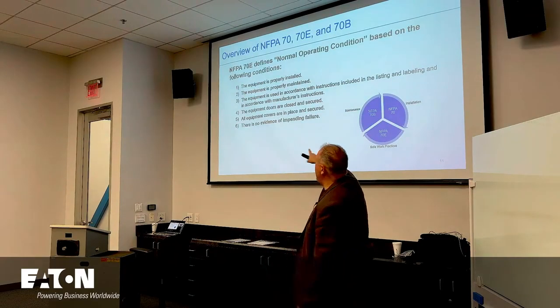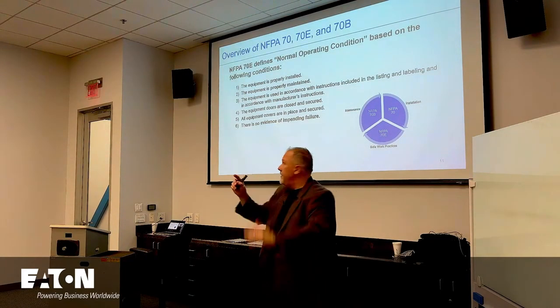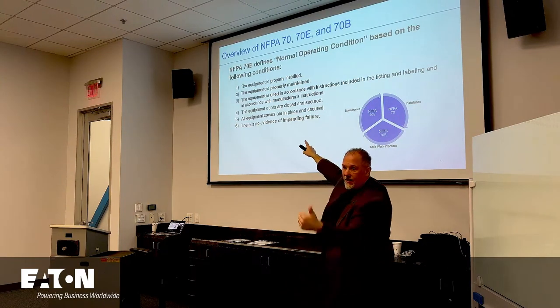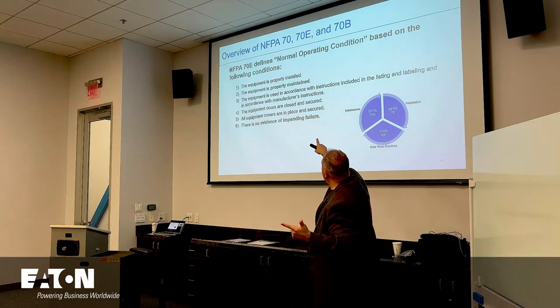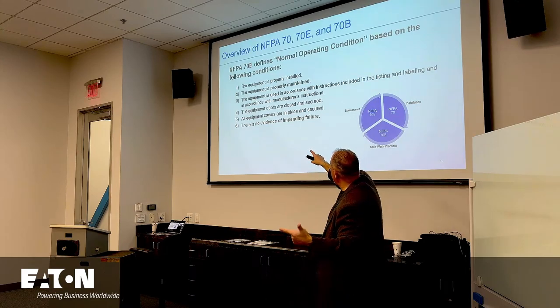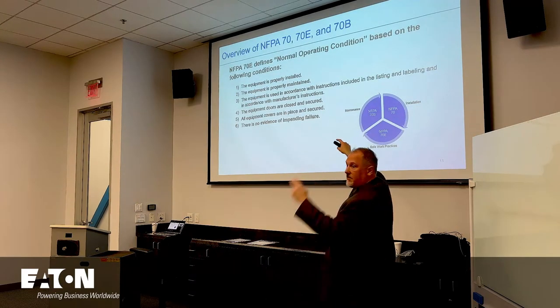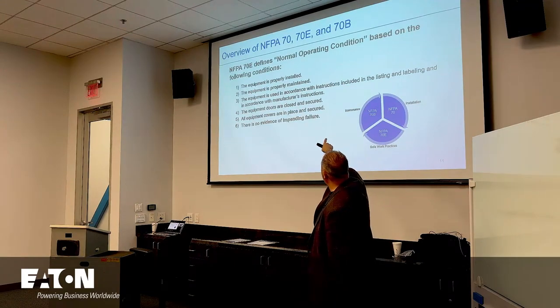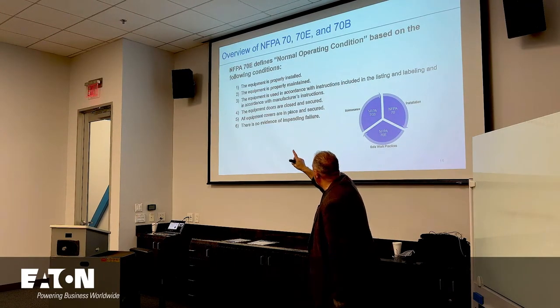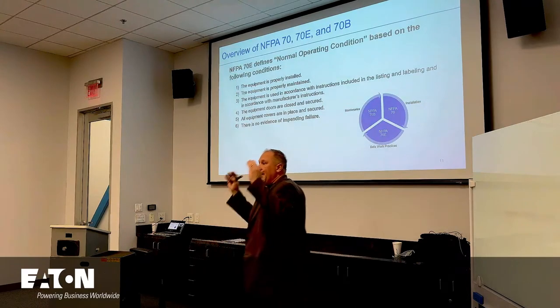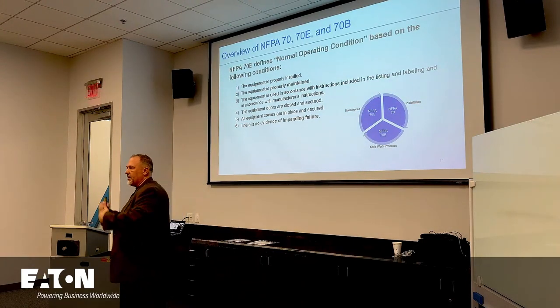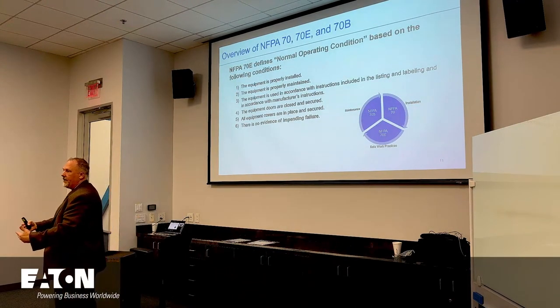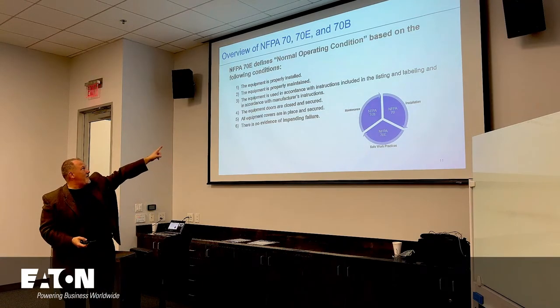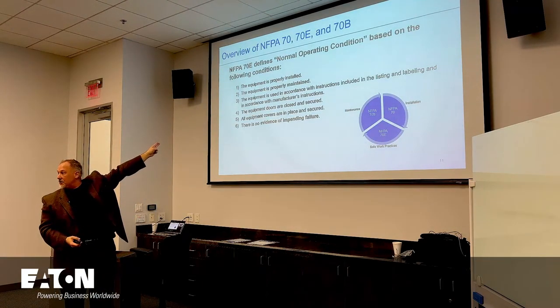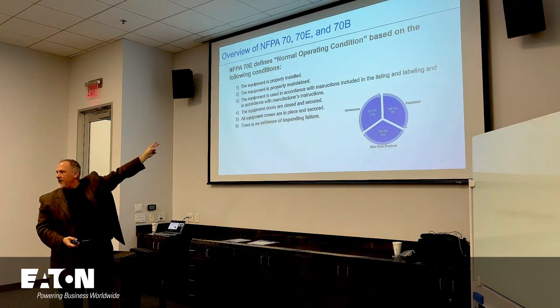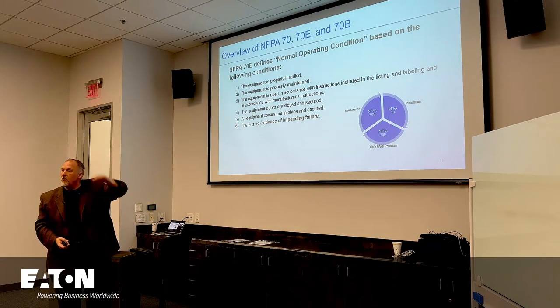So 70E said, look, if it is properly installed per the National Electrical Code, if the equipment is properly maintained per NFPA 70B, the equipment is used in accordance with manufacturer's instructions, the equipment doors are closed and secured, all covers are in place, there is no evidence of impending failure, you don't have a hazardous environment. 70B is part of that, and the National Electrical Code is part of that, in making sure you have a normal operating condition.